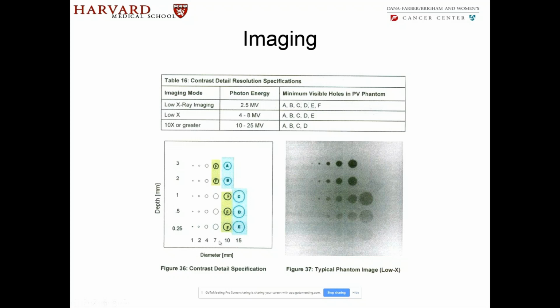So you look at A, B, C, D, E, for example, and up to F should be visible if you're using low X-ray imaging. If you're using low X, 4 to 8, then you should be able to see A, B, C, D, E. You see that A, B, C, D, E, and you say, okay, fine. This is for low X, as an example that I'm showing you here. So this is 4 to 8 MV. Again, this is part of acceptance. All this has to go through before you sign off.